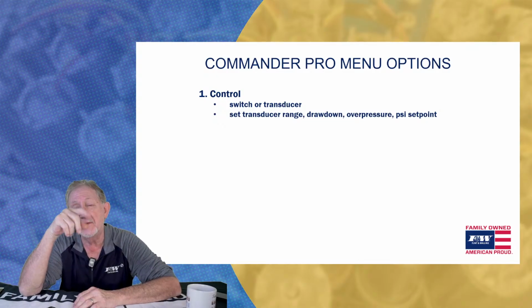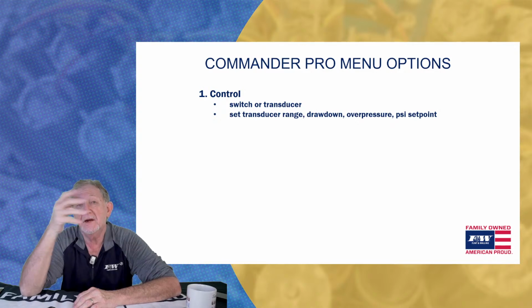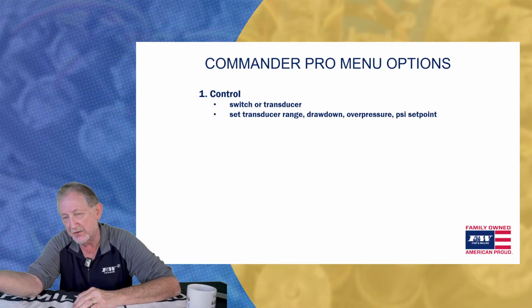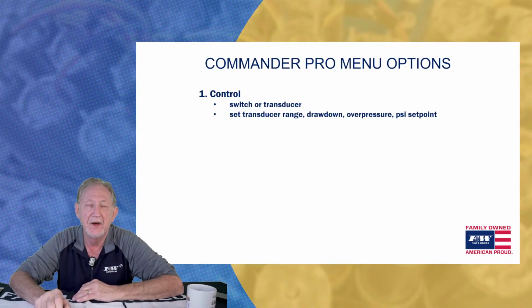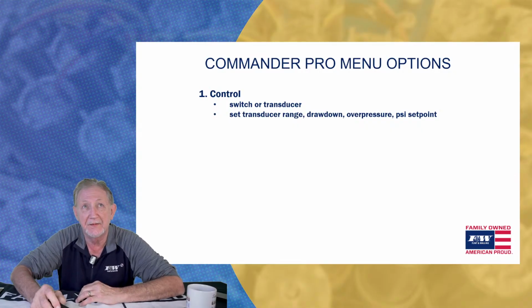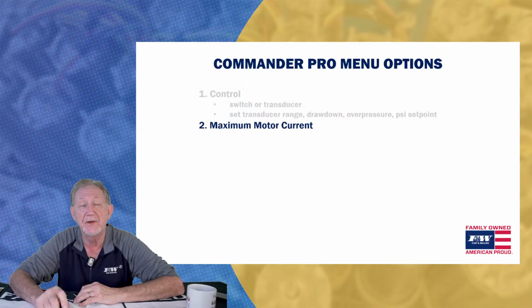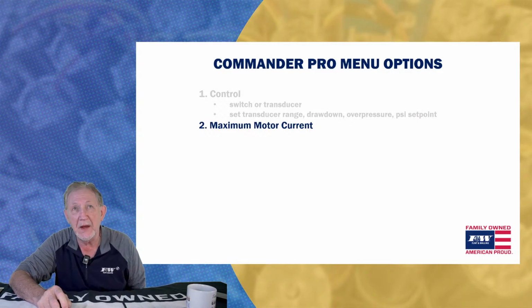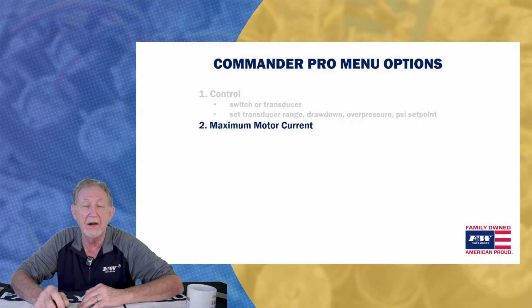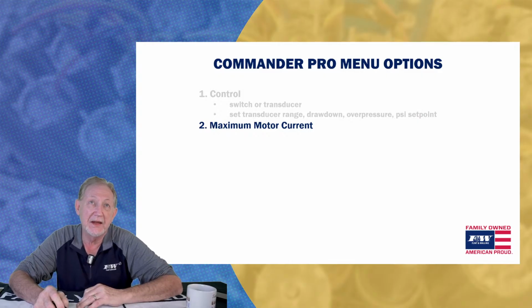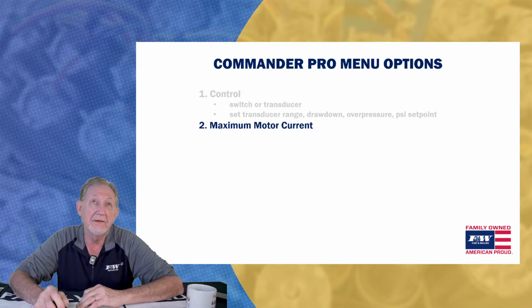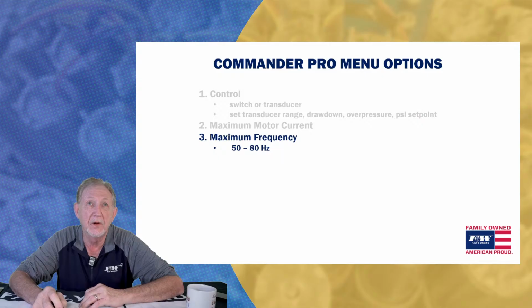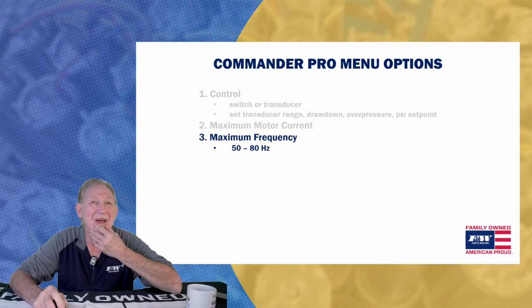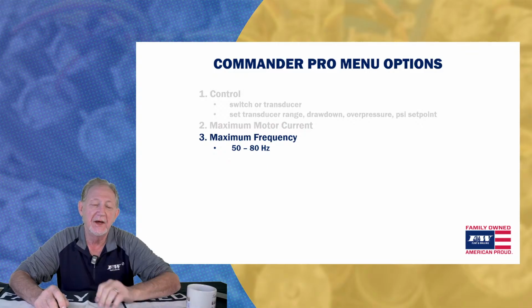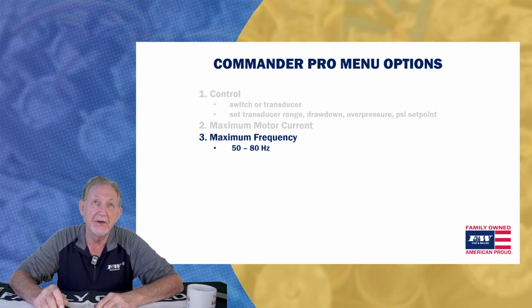To be honest with you, if you don't even tell the drive what you're using, it'll figure it out. It'll come back and tell you, hey, transducer found, or pressure switch found. So it'll detect what we're using, should we not tell it initially. Menu number two is where you plug in your max motor current. That's going to be based on horsepower, and you can use that quick start guide if it happens to be somebody else's motor. Look at whatever their max motor current would be and set it up accordingly.